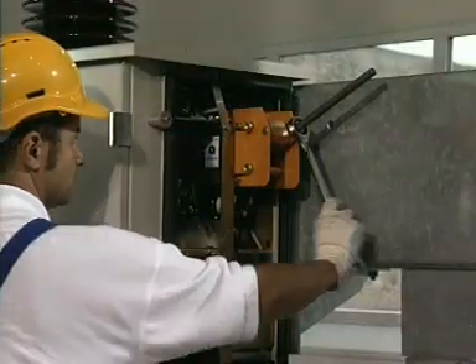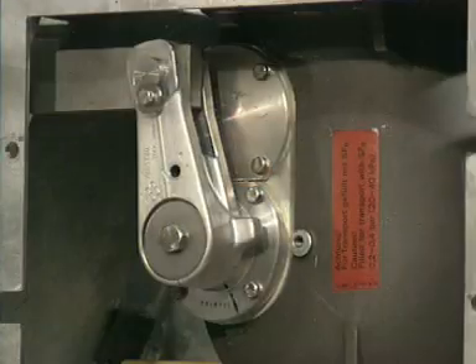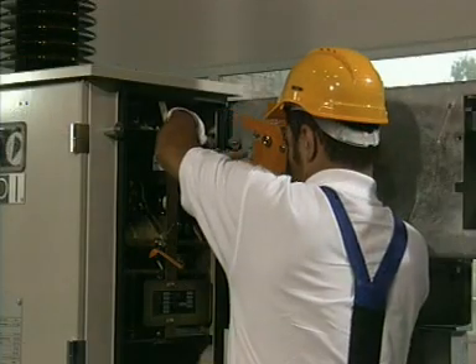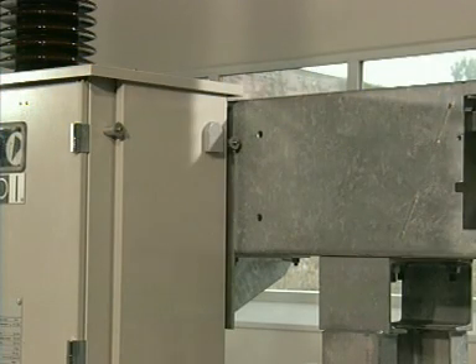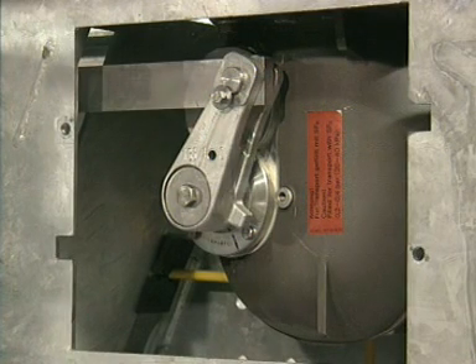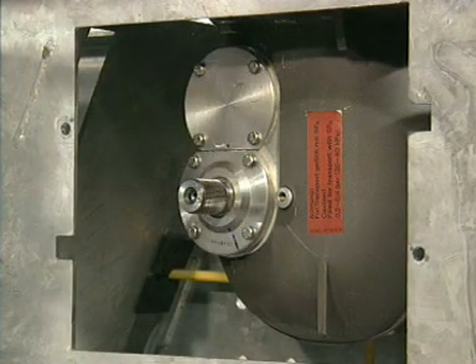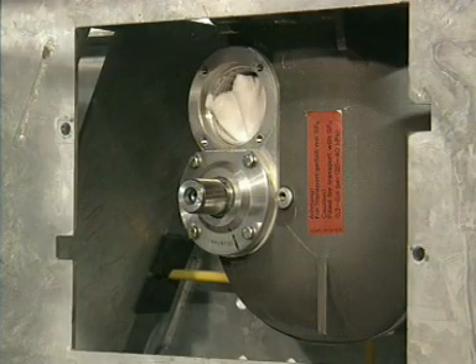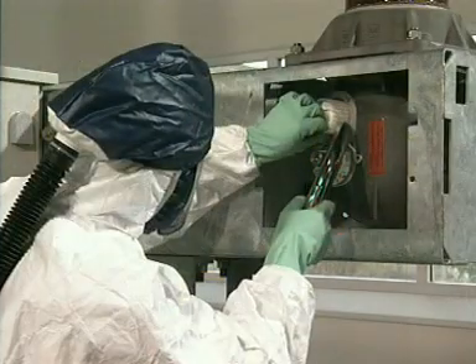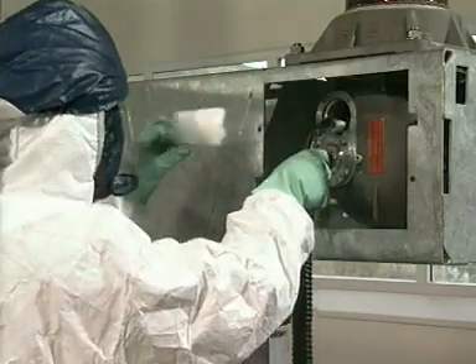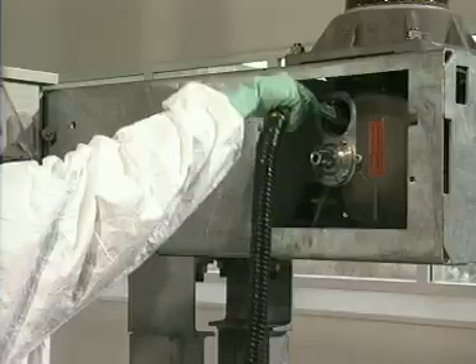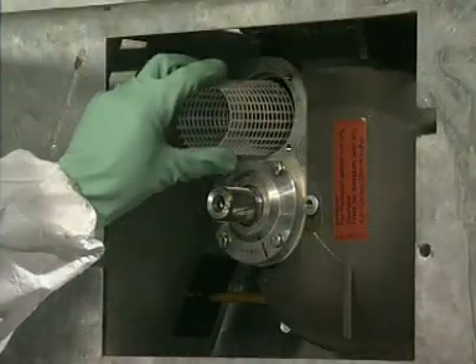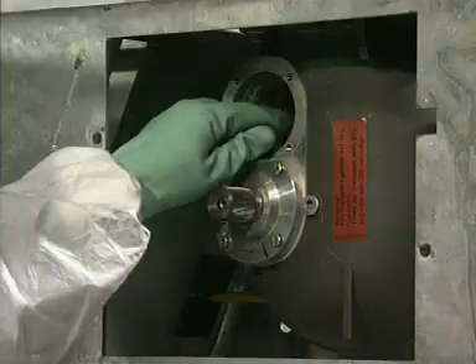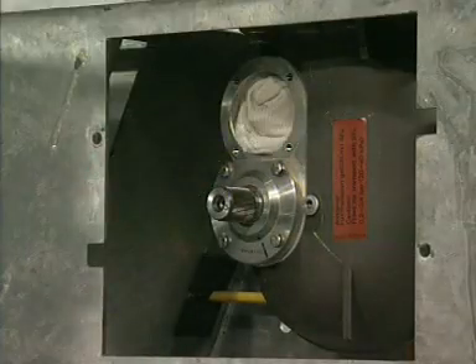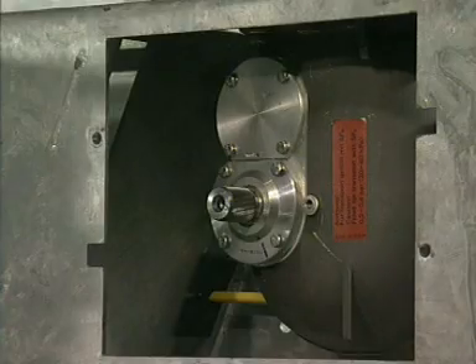Using the low-speed operating device, move the circuit breaker to the open position. Remove both fixtures again and assemble the right side cover. Then remove the connecting rod and lever. Loosen the filter cover on the crankcase. Remove the filter and basket and vacuum it. Vacuum the inside of the crankcase thoroughly. Reinsert the basket and a new filter, close the crankcase with the cover and reassemble the connecting rod and lever. Then evacuate the pole column.